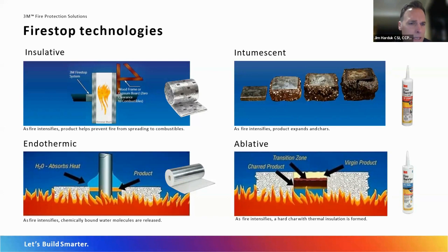Anything that relies on endothermic technology relies on chemically bound water. So basically, that material has water in it, and when it heats up, it releases water molecules, creates steam, and that steam creates a cooling effect on the surface, and it stops the material from burning. And then the last category is ablative. So basically, ablative materials use some type of product that has a very high burnout temperature. Typically, ablative materials are silicone-based. Next slide.